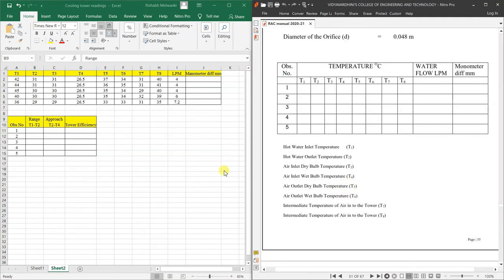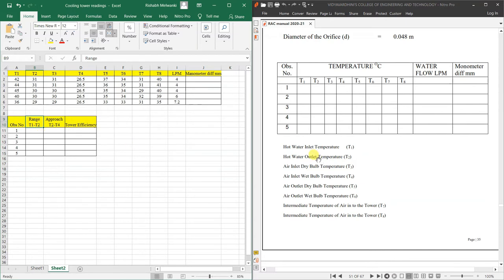The definition of tower range is hot water inlet temperature minus hot water outlet temperature, which is T1 minus T2. Approach is hot water outlet temperature (T2) minus the wet bulb temperature of entering air (T4). So T2 minus T4 is the approach.